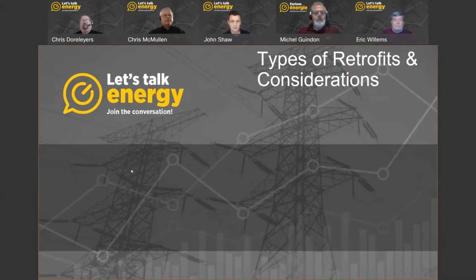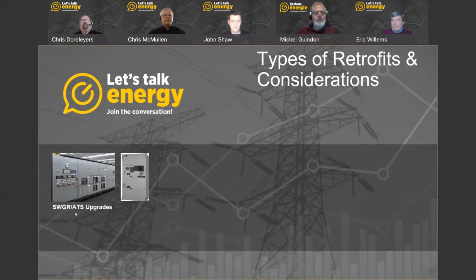Yeah, of course. First one we have is switchgear and ATS upgrades. We may want to change the way our control operates with ongoing changes to the facility or application. Open transition between generator and utility was standard back in the day, but today's requirements benefit from closed transition. Testing becomes seamless. Power outages can catch us off guard, but retransfer back is seamless and predictable in how the facility will behave. We may now want to parallel our generators for their redundancy or increased capacity. We now have the means to operate our generators for global adjustment or to run our units in storm avoidance mode.